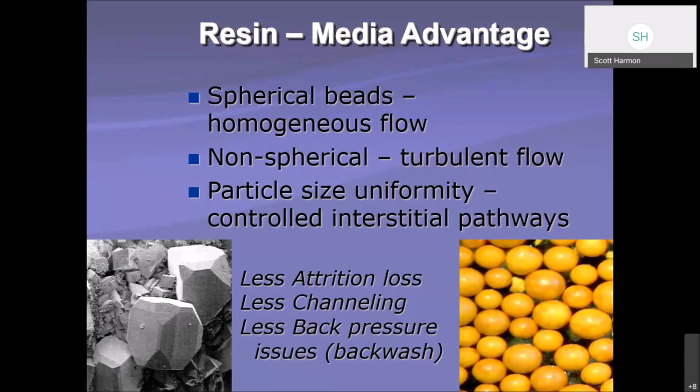If you have a non-spherical or sand-based media, you could have some turbulence issues, which could possibly cause short-circuiting. The particle size uniformity helps control the pathway of the flow through it, which means there'll be more contact with the resins as the water goes through, more of a chance for a particle to adhere to it. That's one of the advantages of using these spherical resin medias.